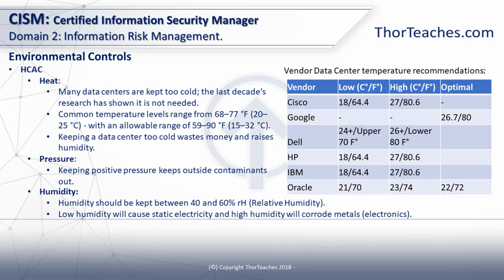We also want to keep a positive pressure inside the data center. What that means is there's a slightly higher air pressure inside the room than there is outside. When someone enters the data center, the air should blow out, not into the data center. And we do this to keep the contaminants out. And we also keep our data centers cleaner than we keep the rest of the building just because of this. In our fire suppression, many of them use the particle density in the air to determine if they should set off the fire suppression or not. So keeping the positive pressure will keep the dust out, and hopefully we can keep our particle levels down and not set anything off inadvertently.